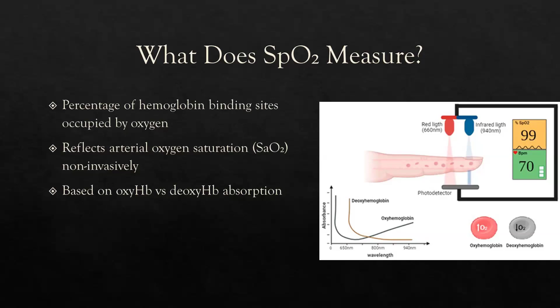And as we see in the picture here, in the pulse oximetry, we have an emitter which sends IR radiations at 2 different wavelengths. One is 660 nanometer and the other 940 nanometer, which are absorbed by 2 different forms of hemoglobin, that is oxyhemoglobin and deoxyhemoglobin. Every liquid has a property to absorb light to some extent, depending on the concentration of the liquid and the kind of liquid. The rest of the light is transmitted, which is received by the receiver on the other hand. Based on the difference between the amount of IR radiation which is absorbed and which is transmitted, we get a reading on the monitor, which gives us an idea about the oxygen saturation.